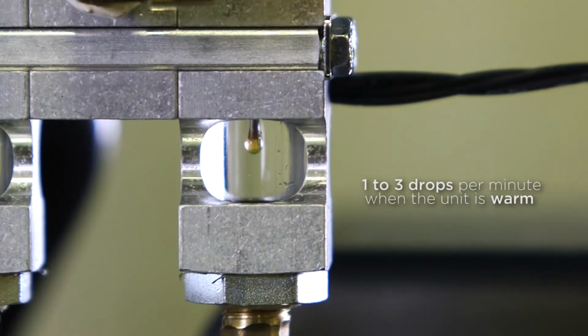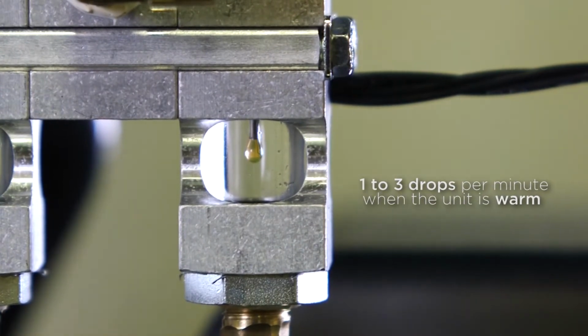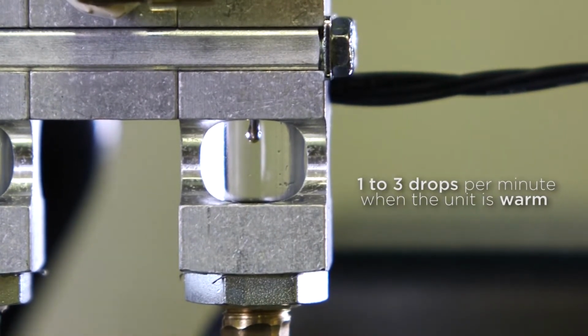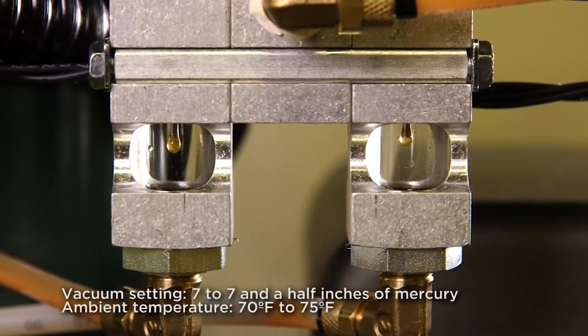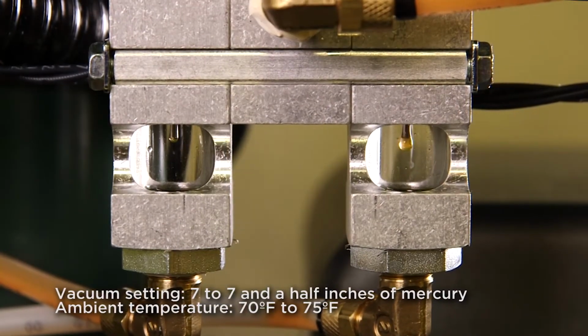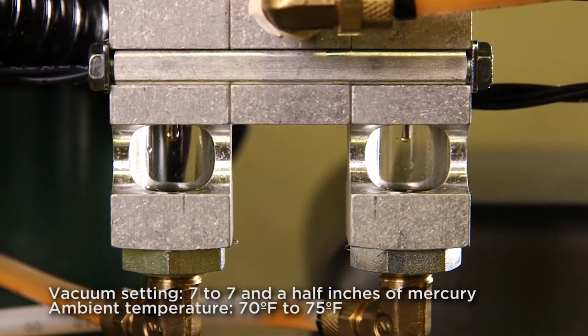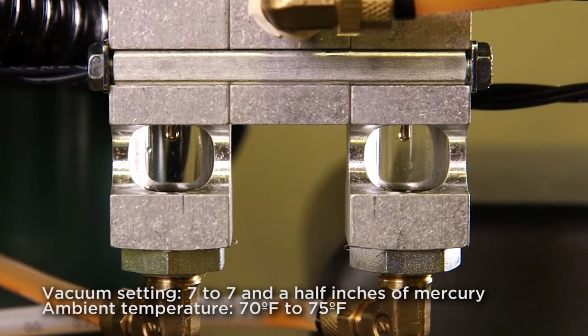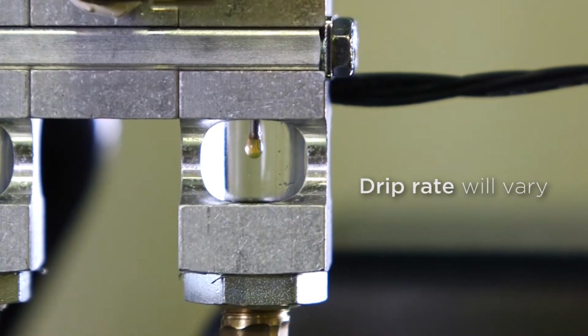The drip rate at each dripper should be 1 to 3 drops per minute when the vacuum unit is thoroughly warmed up. The vacuum setting is 7 to 7.5 inches of mercury, and the ambient temperature is 70 degrees Fahrenheit to 75 degrees Fahrenheit. Please note, the drip rate will vary slightly depending on the ambient temperature and oil temperature.